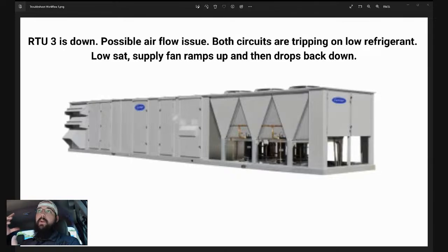The fact that we had a high load, it had been down, but when we came back to turn it on, it settled out at around 40 hertz with a high load and in a high ambient outside. I don't know what his return air temperature was offhand, but it seems weird to me. Something is off about that. Why would we only be running 40 hertz out of 60? So I would expect to run 60 hertz for quite a while.